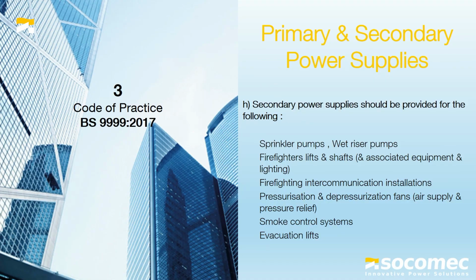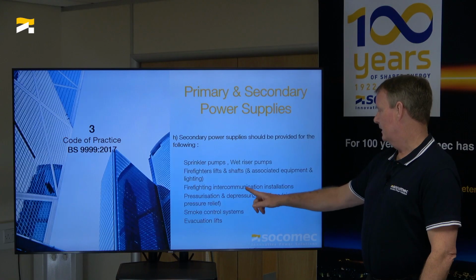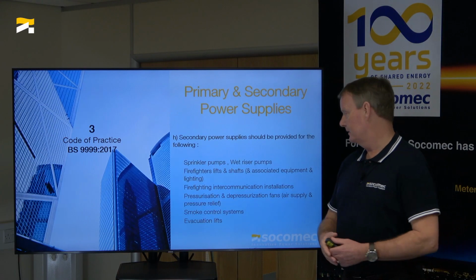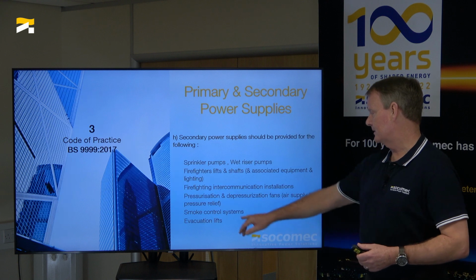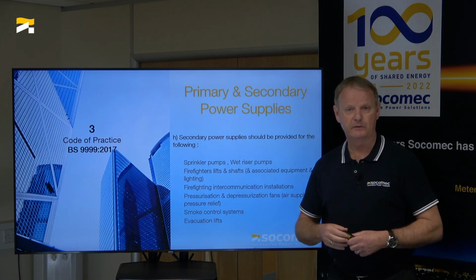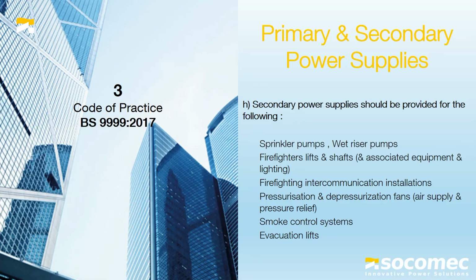So it drills down to secondary power supply. These are the main items it should be able to supply power to. As Richard said, you've got sprinkler pumps, firefighter lifts, shafts, communication systems, smoke control, because you need exhaust fans to come on and supply fans to stop.